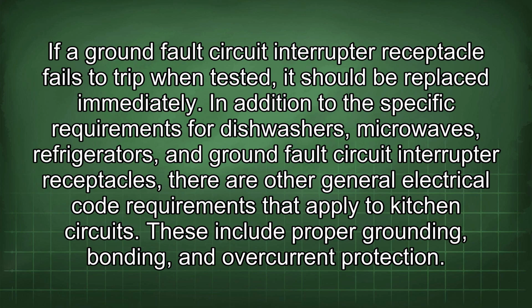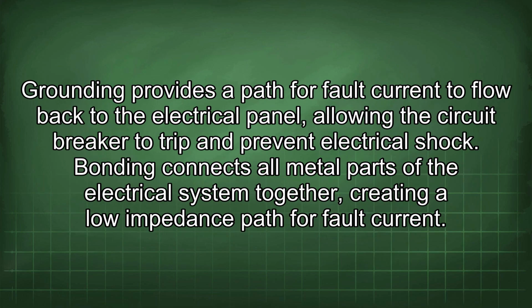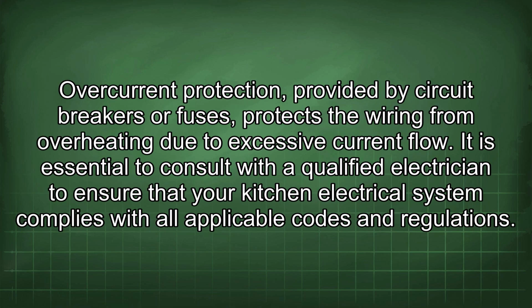In addition to the specific requirements for dishwashers, microwaves, refrigerators, and ground fault circuit interrupter receptacles, there are other general electrical code requirements that apply to kitchen circuits. These include proper grounding, bonding, and overcurrent protection. Grounding provides a path for fault current to flow back to the electrical panel, allowing the circuit breaker to trip and prevent electrical shock. Bonding connects all metal parts of the electrical system together, creating a low impedance path for fault current. Overcurrent protection, provided by circuit breakers or fuses, protects the wiring from overheating due to excessive current flow.